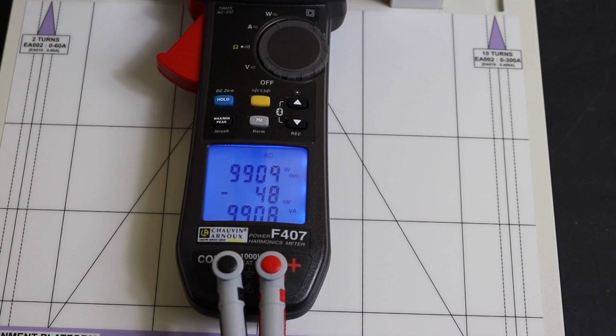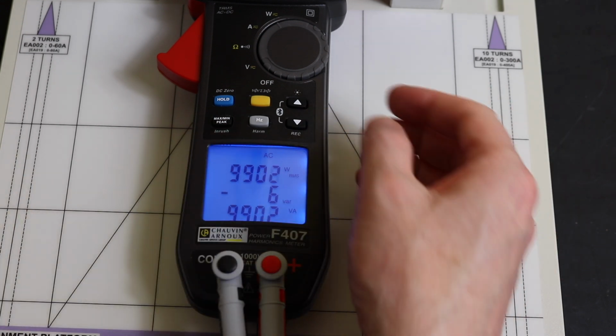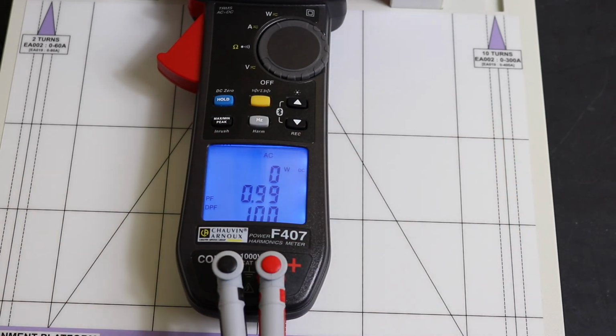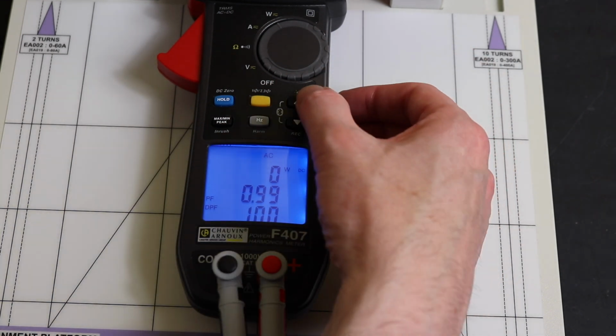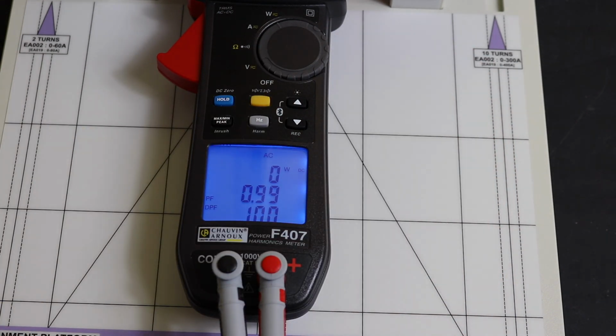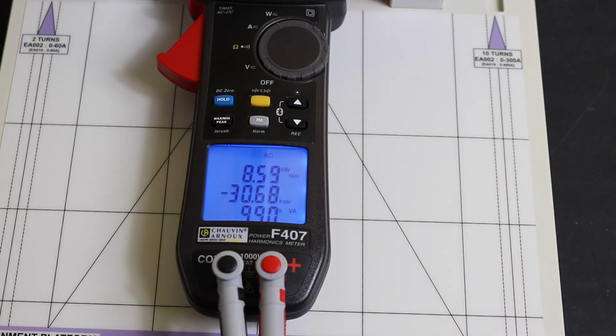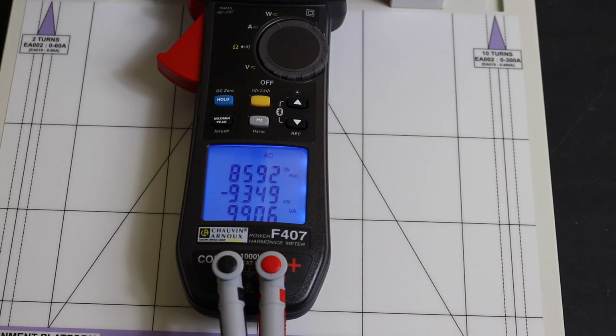We are injecting 10 kilowatts, and we are reading 9.9 kilowatts or 9,900 watts there, so a little bit down, a little bit of reactive power in there. But our VA is matching our watts. With the arrow key here, you can move between the two displays to get power factor up, which is obviously 0.99. I'll just change the screen to give me minus 30, so that should give me a power factor of 0.86, which is good. Obviously our power has now dropped down to around about 8,600 watts. Our reactive power has come up now, but our VA has stayed the same there. So that's the power functionality.